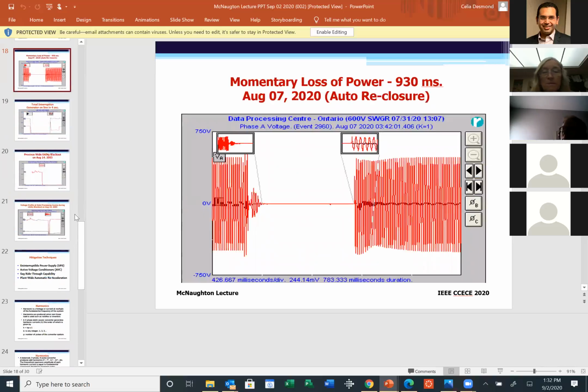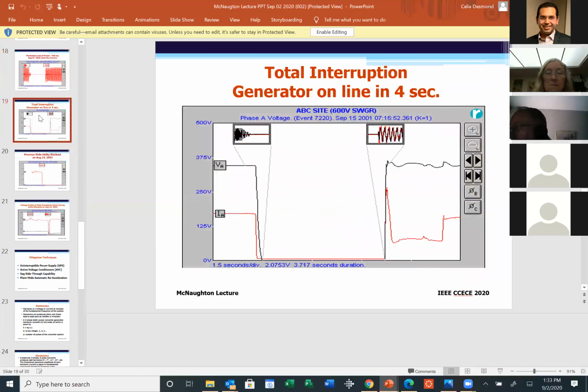This is what I wanted to share with you. This is what I call hot off the press. Look at the date of this slide, August 7, 2020, less than a month ago. This is what we call a momentary outage. This particular site experienced a complete loss of power, and the power was restored in less than 1 second. If the mitigation equipment available in this site did not operate, they would have an enormous amount of loss of business and potentially even a restart. Next slide, please.